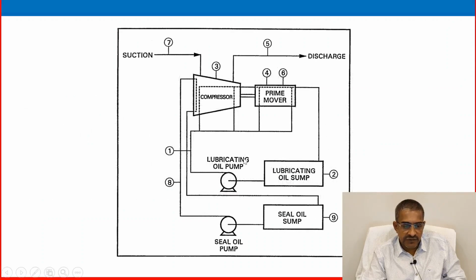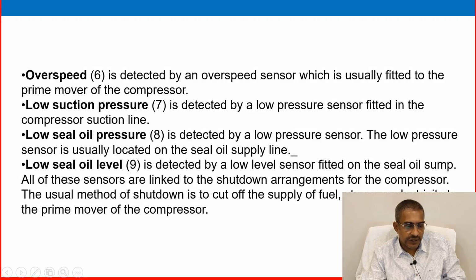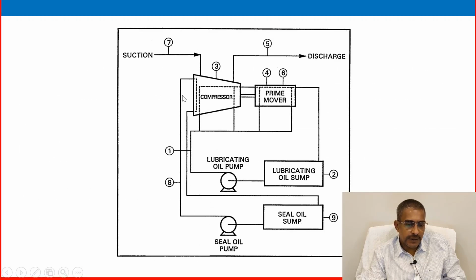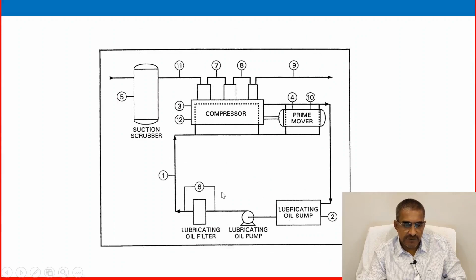And this is the picture which is representing 1/2, 1 and 2, then 3, then 4, then 5, 6, then 7, then 8 and 9, just to cross check the numbers and the corresponding trip conditions. And when you go to your field, your compressor area, please cross check that these are available, or these are the protection devices provided there, or anything additionally available there to reconfirm. Then you will get a better idea of the compressor safeguarding system, we can say. So this is another picture of the same kind.